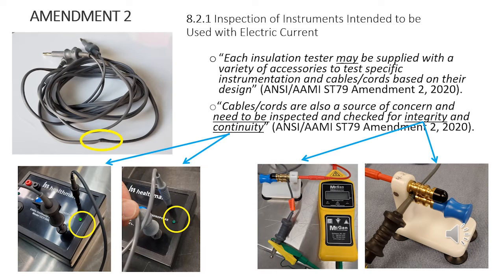Like the picture on the right, you can see it went off, so there was some break in there. If there is a full break, the light will never go on. If there is a half break or multiple half breaks, that's when the light will flicker. The cable continuity tester can actually test bipolar cables and cords as well.